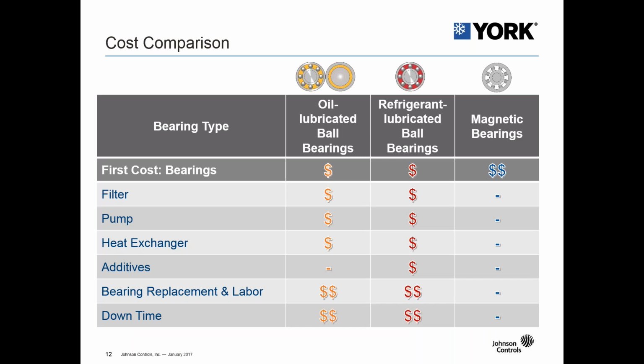So let's take a look at a cost comparison. We have the oil lubricated on the left, the refrigerant lubricated ball bearings on the right, and the magnetic bearings. So it's very clear the first cost of the mag bearings is the most expensive. However, we've seen significant reduction in costs over the past decade of magnetic bearings, which is why they're becoming more commercially available, and we're seeing them used in many different applications, not just chillers.